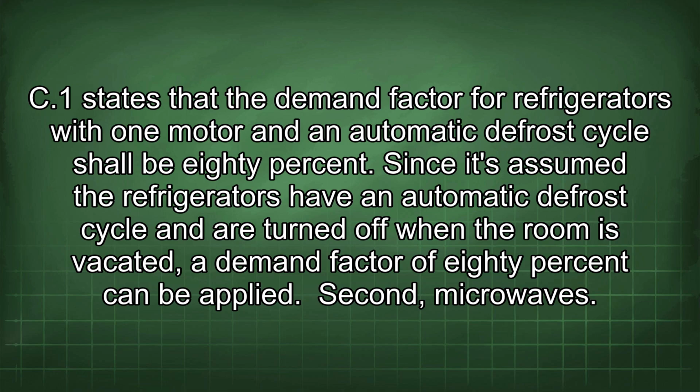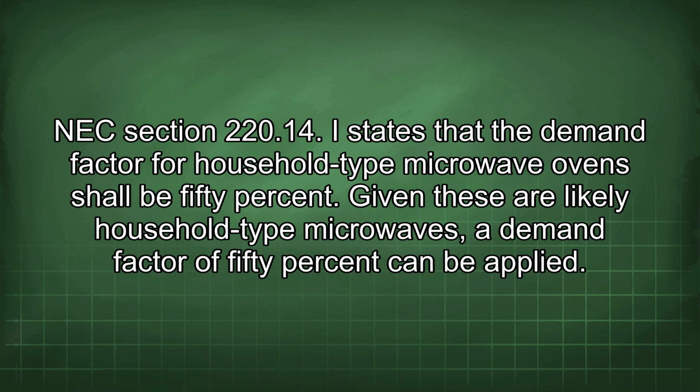Second, microwaves. NEC Section 220.14.I states that the demand factor for household-type microwave ovens shall be 50%. Given these are likely household-type microwaves, a demand factor of 50% can be applied.